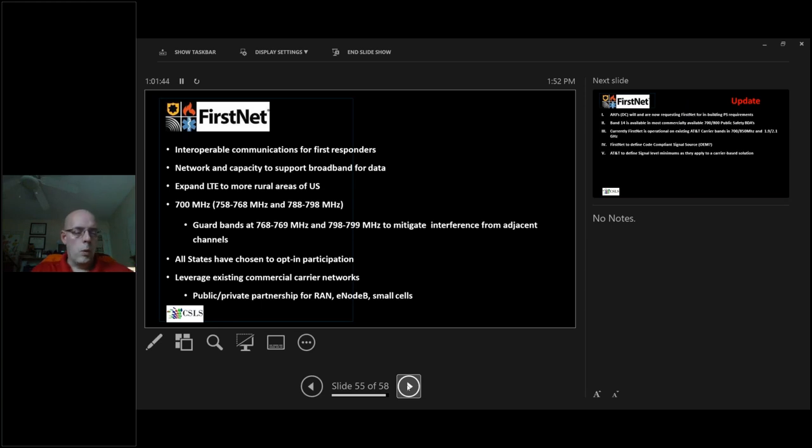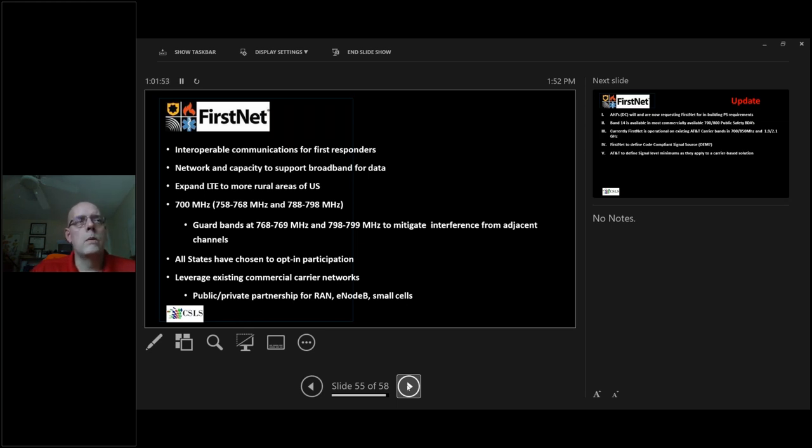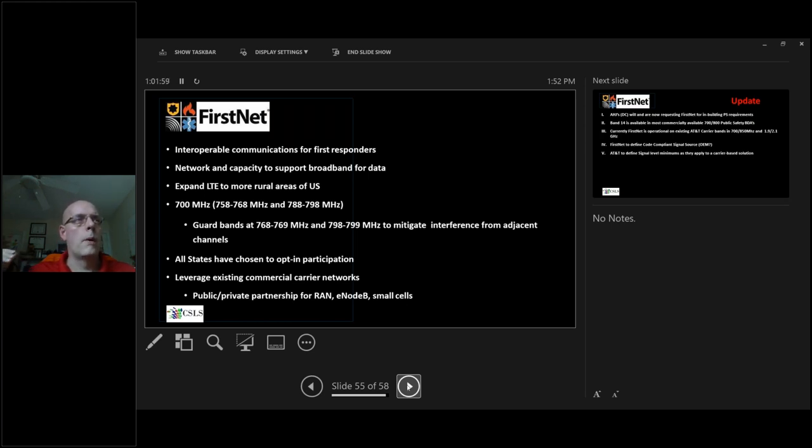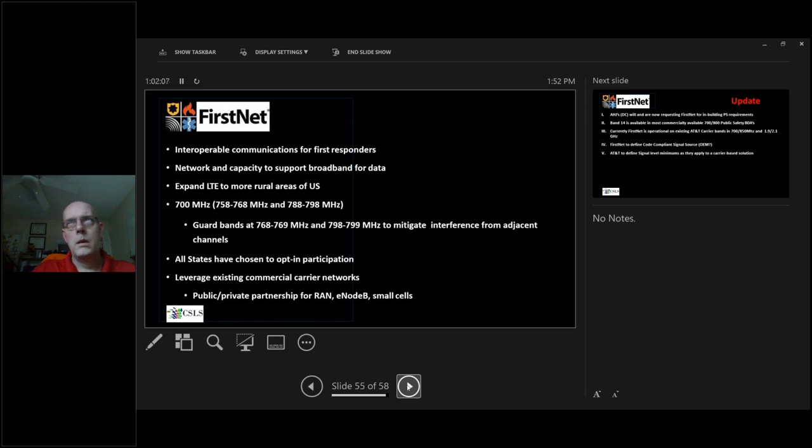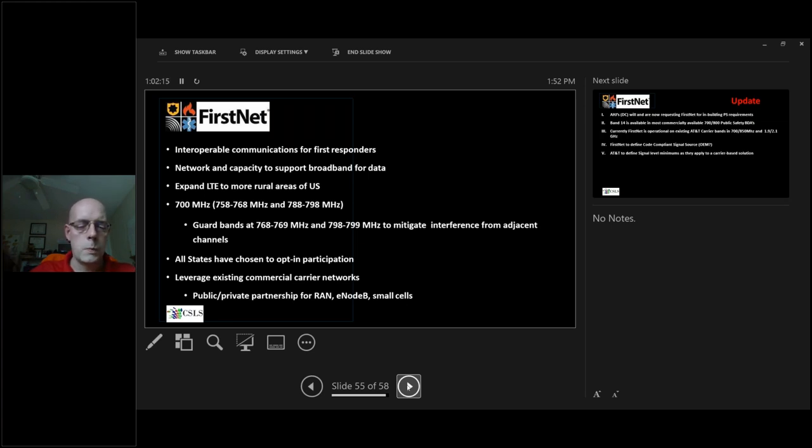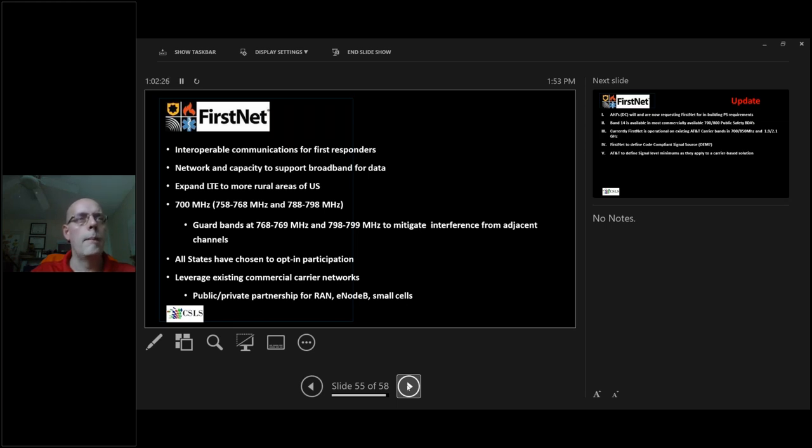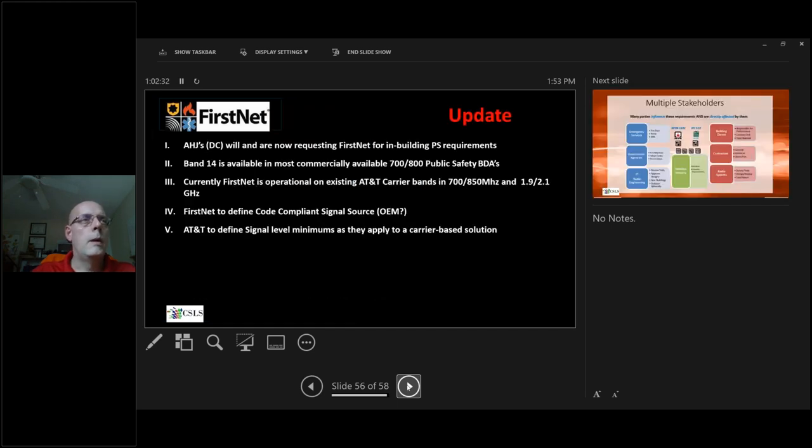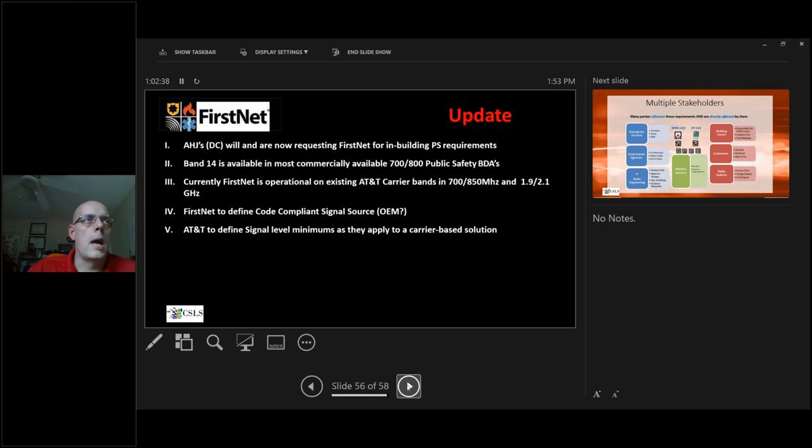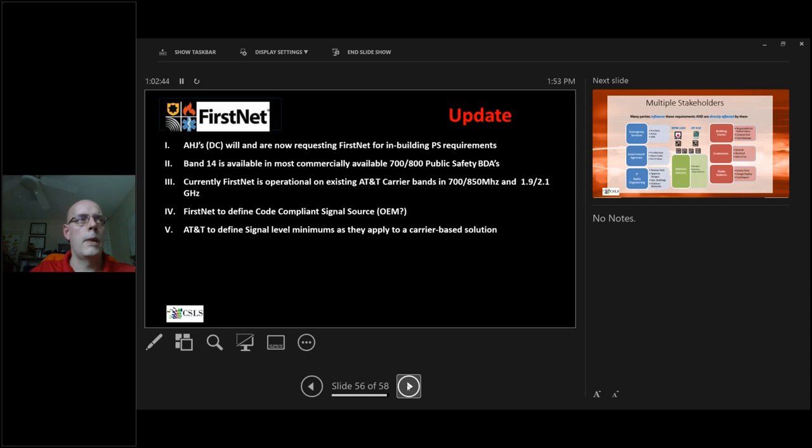The other really key important thing to talk about is FirstNet. FirstNet was a contract awarded to AT&T back in 2015 to create a national, based-on LTE telephony system for first responders to be able to communicate across the United States. AT&T has made great strides in the last seven years of installing the necessary equipment to make FirstNet available throughout the United States. It's now left, for the most part, to the local jurisdictions, the states themselves, to decide whether or not they're going to opt in or opt out. We are required from the emergency responder radio communication system to install bidirectional amplifiers that are FirstNet capable. It's really important, if you're an AHJ, to make sure that the BDAs being utilized in their cut sheets have the FirstNet system as part of the design of the system itself and it's compliant.